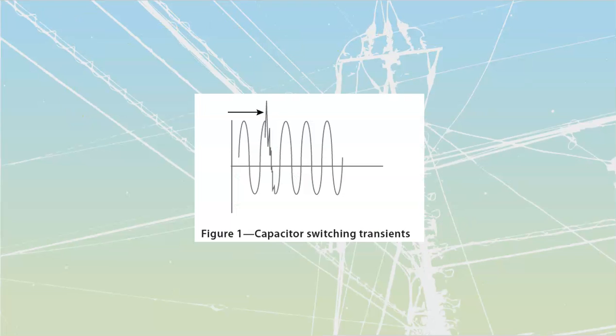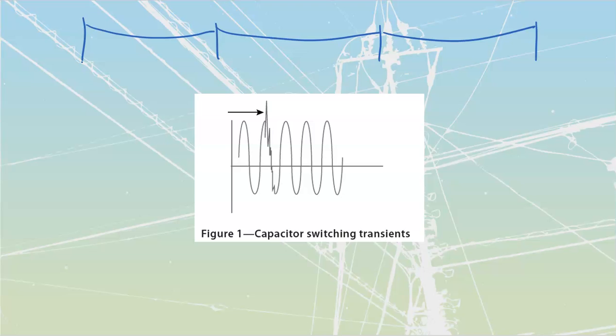Capacitor bank switching also causes issues. We use a lot of capacitor banks whenever we need to offset inductive loads. BC Hydro penalizes us and our customers for inductive loads, but they've got their own inductance on the system from all the transformers used to transform different voltage levels, as well as from the transmission lines themselves, each of which has inductance. So every once in a while they put on a capacitor bank designed to counteract that.